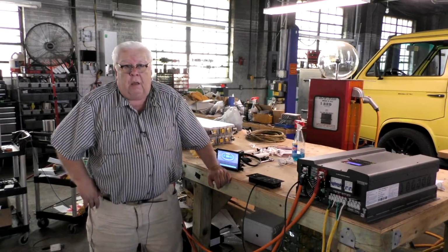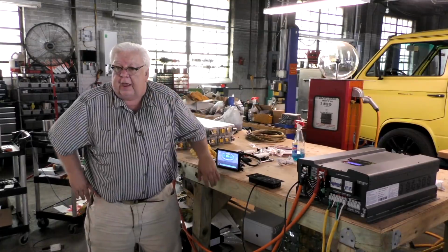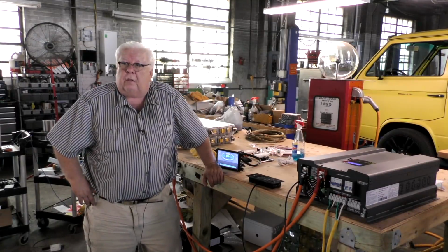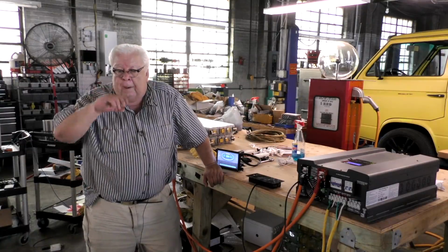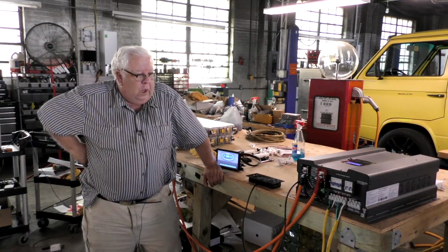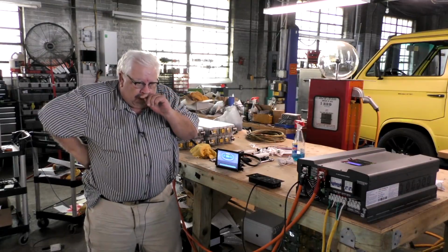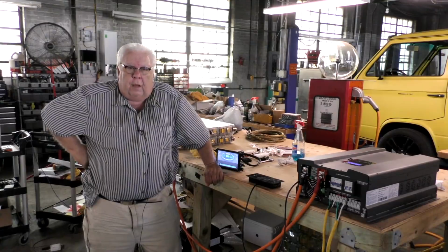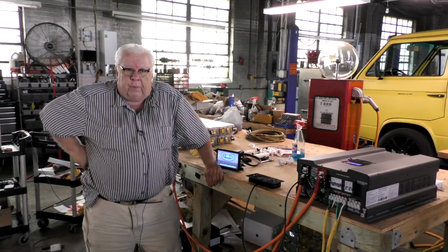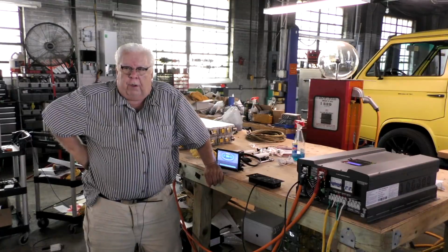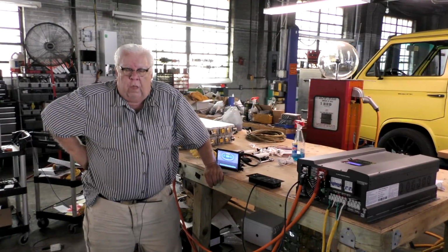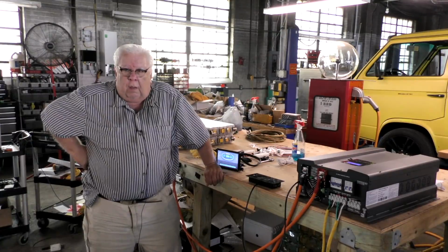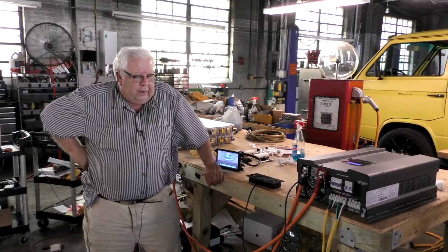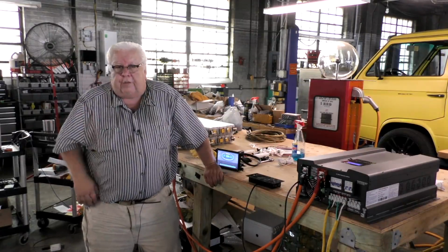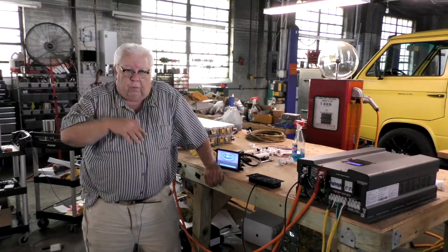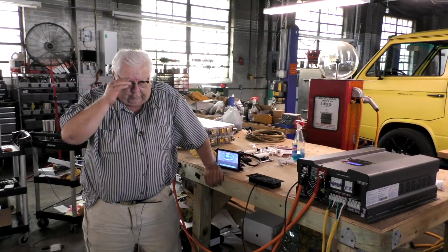We're going to do a project with a big enclosure. As I say, an 85 kilowatt, about an 80 kilowatt hour battery, 16 Model S modules, this inverter, and probably cool it because who knows how big a solar system they'll want to tie that into. But kind of the mother of all 48 volt Tesla-based solar systems. And the key feature of it, you can still do DC coupling. You simply take charge controllers, run your photovoltaics to the battery terminals.